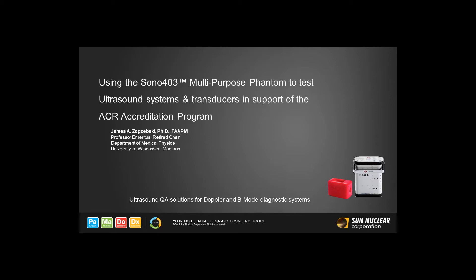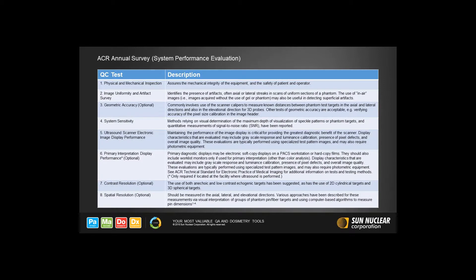How may the Sono403 Phantom be used in ultrasound quality assurance to meet ACR lab accreditation requirements? The ACR website lists and gives a brief description of eight tests to consider in required annual surveys of ultrasound scanners. Some of these tests are optional and some of them are required.